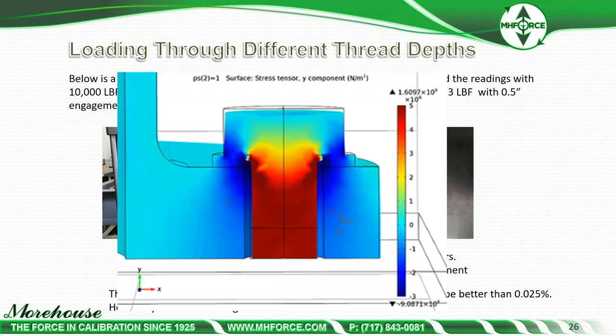If you have cells with threads in them, are you sending the adapters you use for calibration with the instrumentation? If you're not, chances are there's a large error and you're not replicating what the calibration lab did. Your results are not going to match. Different thread engagement depths produce different stress distributions through the inner workings of the load cell.